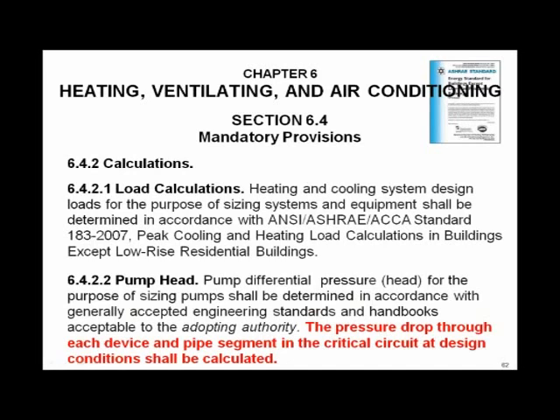Now, as I look a little bit deeper into 90.1 2010, I see some things that are going to impact cooling tower piping even more. Look at the pump head. Look at the bottom there in red. The pressure drop through each device and pipe segment in the critical circuit at design conditions shall be calculated. In other words, no more rule of thumb on a pump head for condenser water pump. We've got to do this right. We've got to detail it out, take it off, and do detailed pump head loss calculations. We maybe have a problem here. Just pay attention to this. It needs to be in the file. This is a change that we've got to start paying attention to.